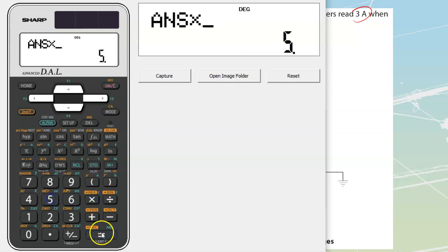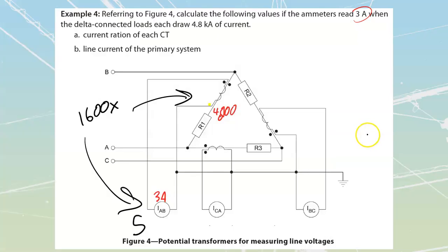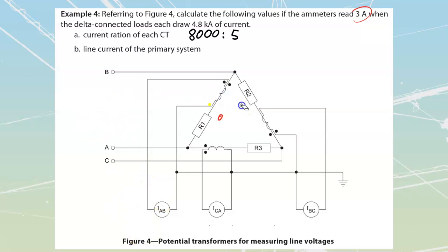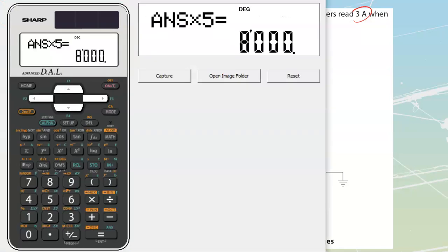1,600 times 5 gets me out to a value of 8,000. So my current ratio is going to be 8,000 to 5. What's my line current on the primary system? Line current on the primary system, we don't need to use the CT to do any of that. We just have to take a look at what we have for current inside here, 4,800. And because it is a delta type of system, we know that these currents are going to be adding together to form something greater. Let's go and do that.